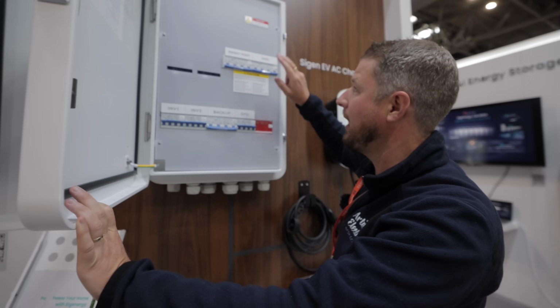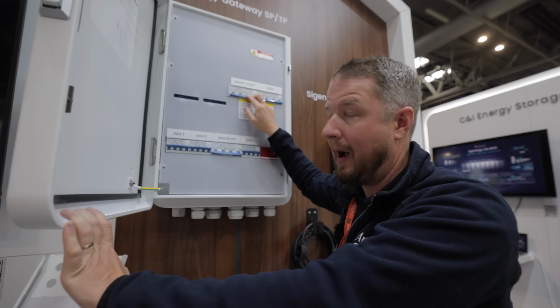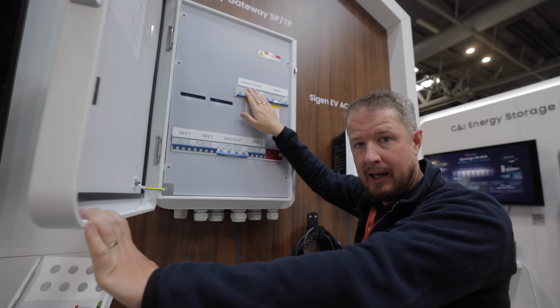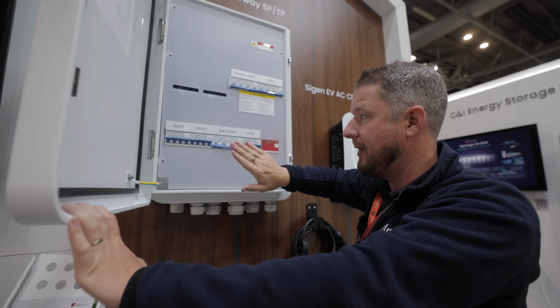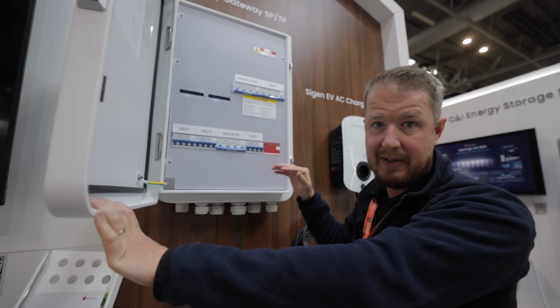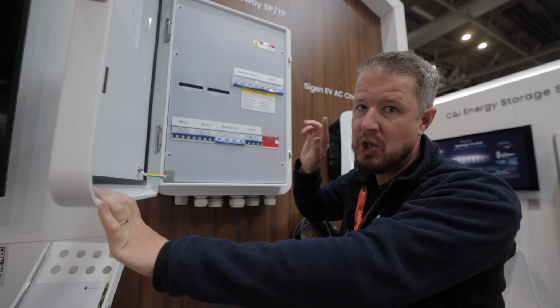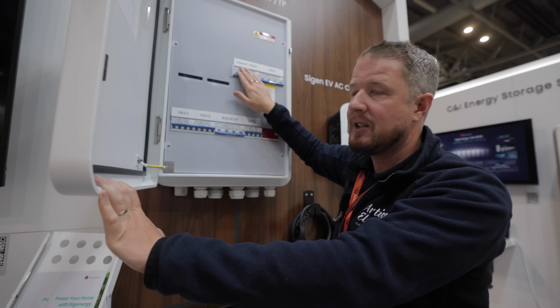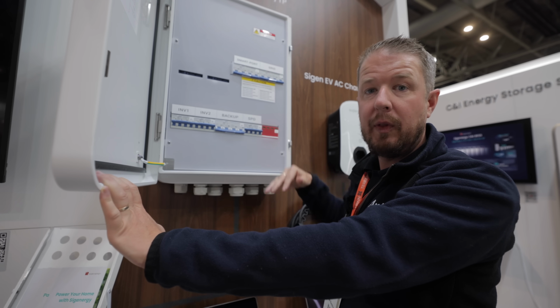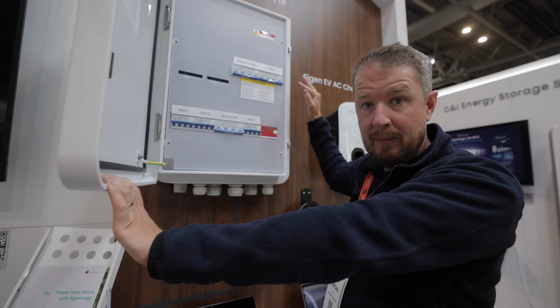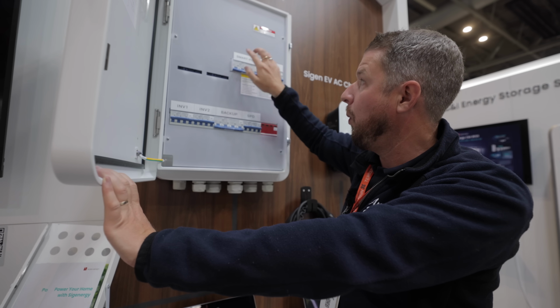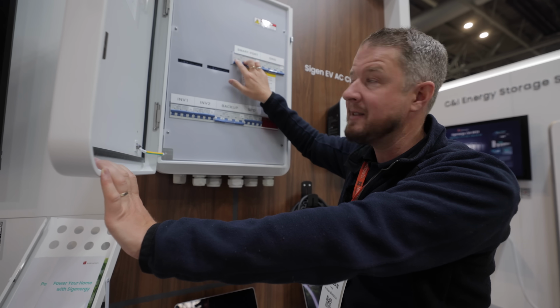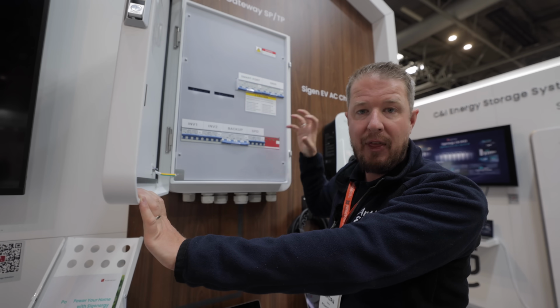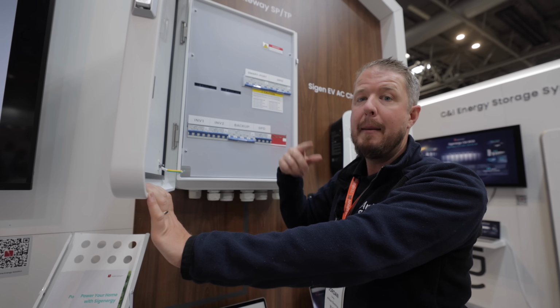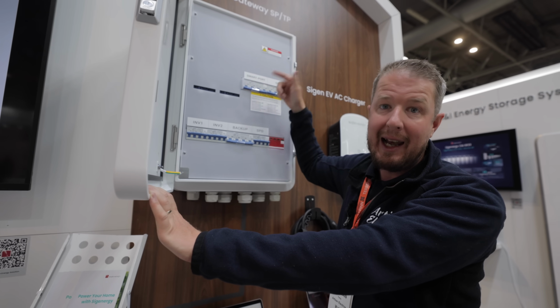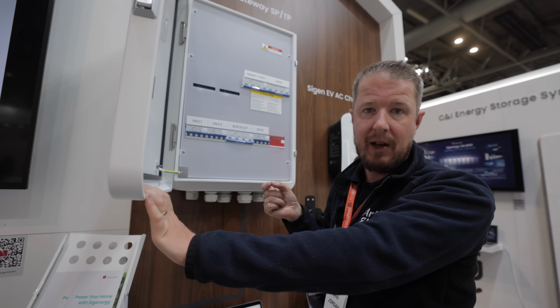This is a smart port in the gateway. What we had done is connect the third-party inverter, along with all the electrics in the house, off the backup side of the gateway - but we shouldn't have done that. We needed to wire it up off the smart port. So we pulled the tails out from the meter, from the generation meter, and wired them into the smart port. That allows you to add the third-party inverter as a separate device and monitor through this smart breaker exactly how much power it's using.